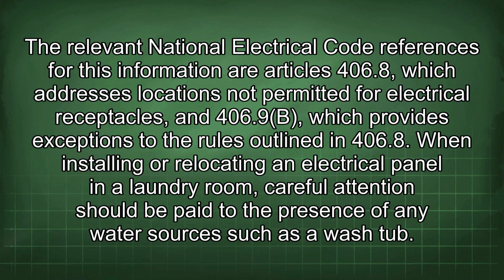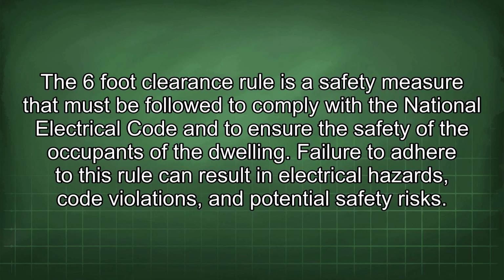When installing or relocating an electrical panel in a laundry room, careful attention should be paid to the presence of any water sources such as a wash tub. The 6-foot clearance rule is a safety measure that must be followed to comply with the National Electrical Code and to ensure the safety of the occupants of the dwelling. Failure to adhere to this rule can result in electrical hazards, code violations, and potential safety risks.